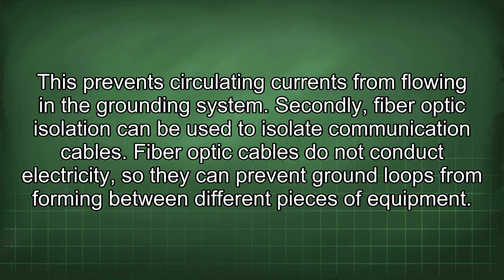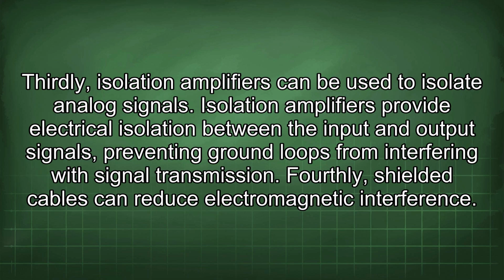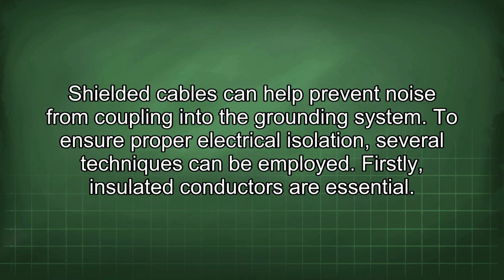Secondly, fiber optic isolation can be used to isolate communication cables. Fiber optic cables do not conduct electricity, so they can prevent ground loops from forming between different pieces of equipment. Thirdly, isolation amplifiers can be used to isolate analog signals. Isolation amplifiers provide electrical isolation between the input and output signals, preventing ground loops from interfering with signal transmission. Fourthly, shielded cables can reduce electromagnetic interference. Shielded cables can help prevent noise from coupling into the grounding system.